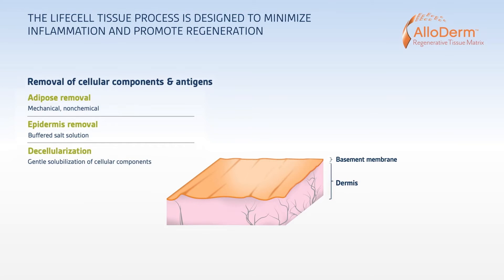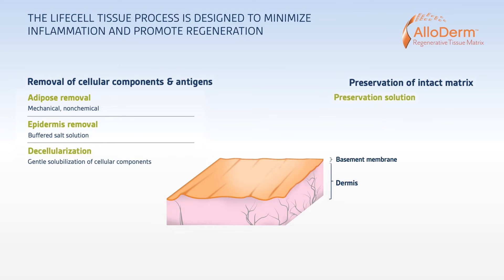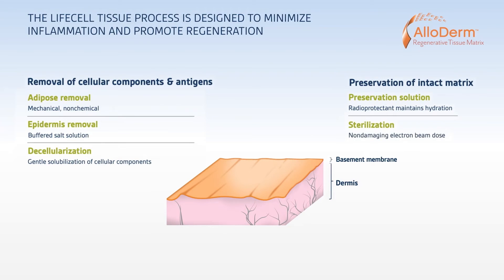The remaining undamaged tissue is preserved for packaging, sterilization, and storage. We place the tissue into a radioprotectant preservation solution to maintain hydration and protect the tissue during the final step, sterilization. Our low-dose electron beam sterilization process was extensively tested to optimize both the method and dose in order to maintain tissue integrity.